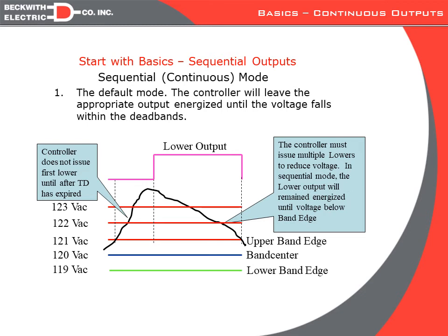But we have regulator manufacturers now, such as the Cooper Quick Drive, where they can tap in 1/4 of a second. So in 1 second, it can take 4 taps. Well, 4 taps at 3/4 of a volt per tap is enough to drive through band. So what can happen is, I am lowering, and by the time I determine that I've gone low enough in band, I've taken another couple additional taps, and now I may be too low and have to come back up.